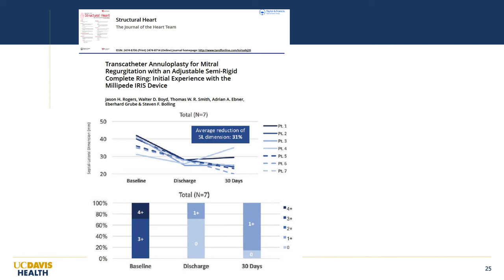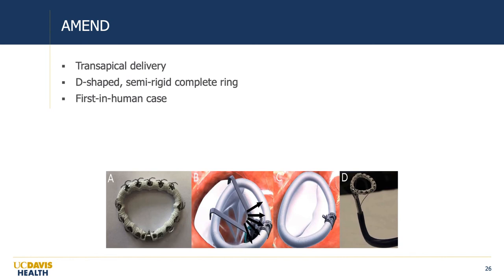The third direct annuloplasty device is the Amend system, which uses a transapical delivery approach. The device can reform through the catheter into a rigid D-shaped complete ring, with a series of anchors extruded from the device for initial posterior anchoring, then the device is pulled forward to the anterior annulus and fully anchored. A first-in-human case has been reported.